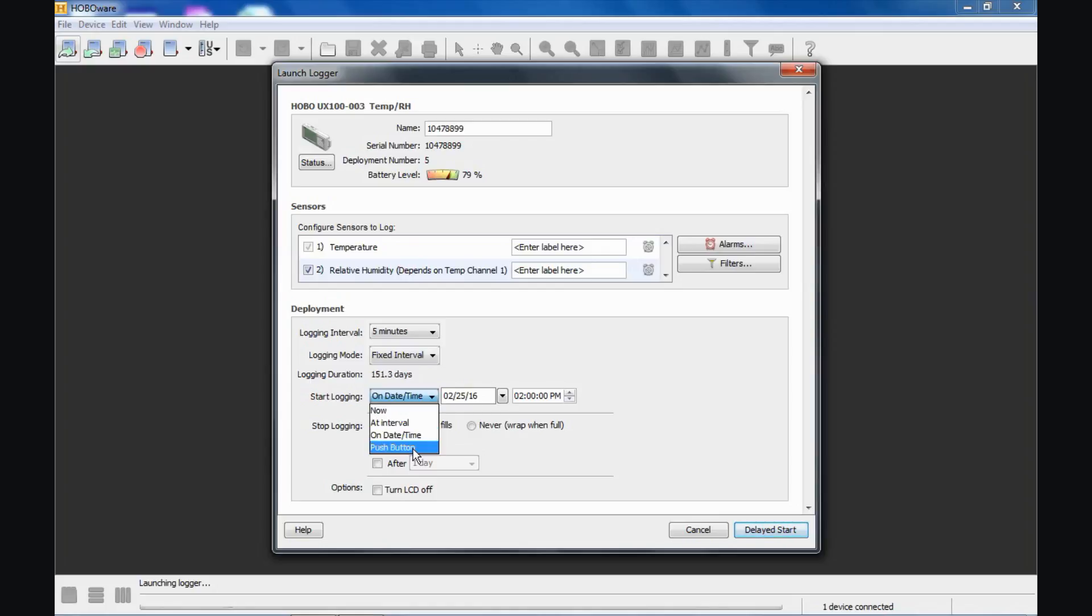Also, this logger has a push button on it, so you can take advantage of that push button by selecting push button start, and then you can basically click start, click button start on the launch screen here. Take your logger to its location, press and hold that button for three seconds, and the logger will begin logging then.